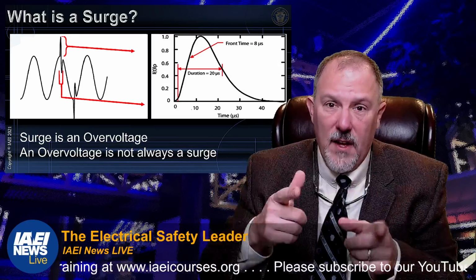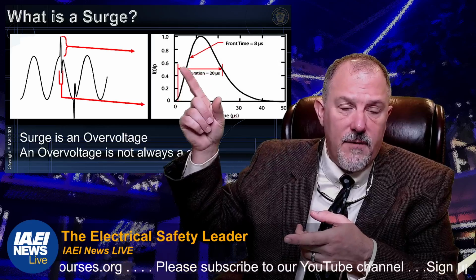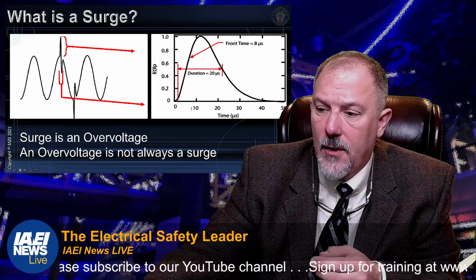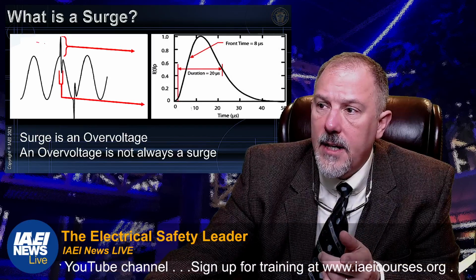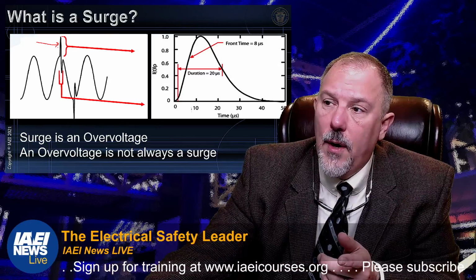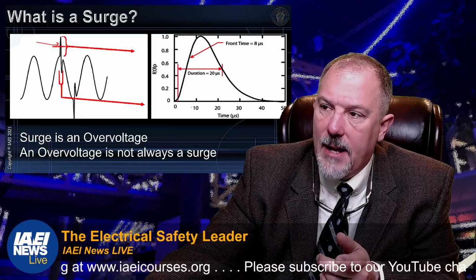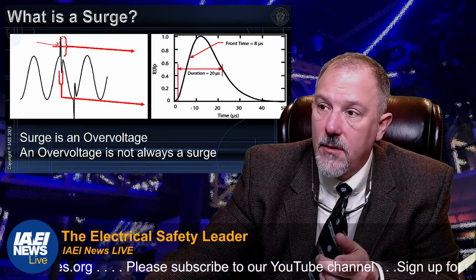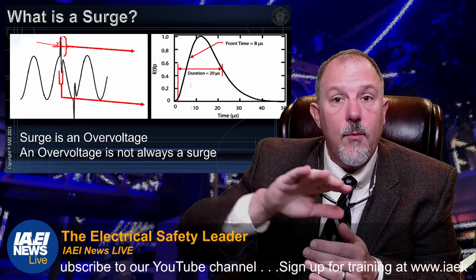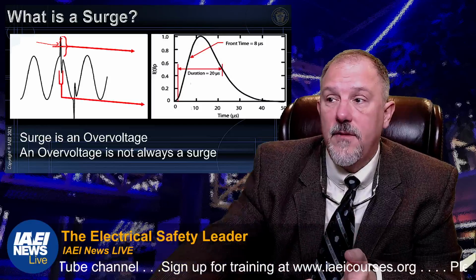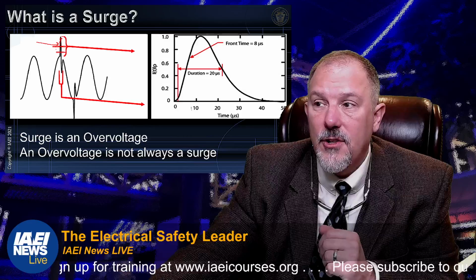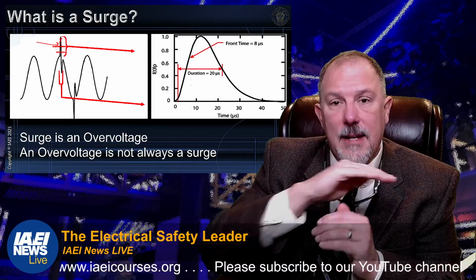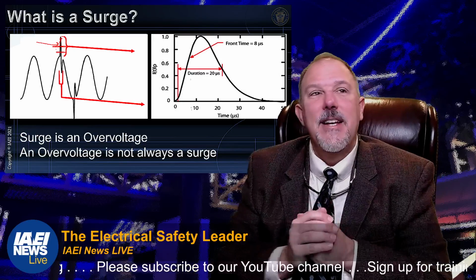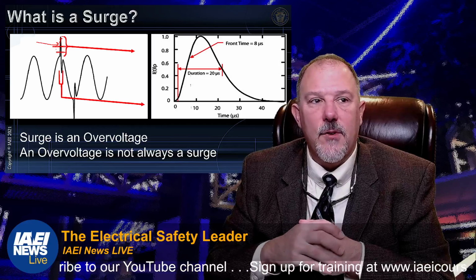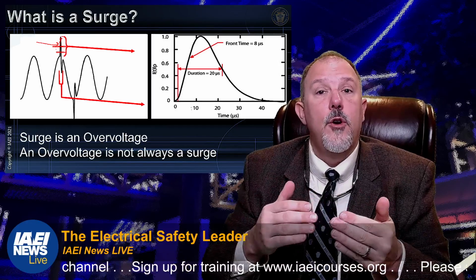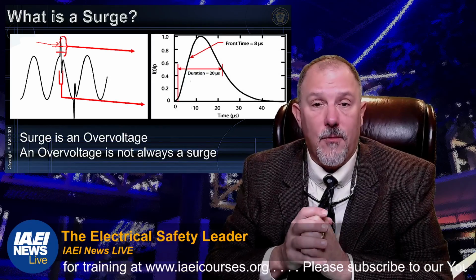If you think about what you're seeing here, you have this transient voltage that's up pretty high in the system. Say this event right here is at your service equipment. If you have a transient voltage device that clips that off at that point, making that go away, you're still left with a transient event over that sine wave that will propel itself, that will be seen downstream. And downstream devices might be able to clip these at lower values. So that clamping capability is an important aspect. Technically, we consider it as clamping that voltage peak, but technically we're shunting current to ground, right? We're moving the current around that it's generating as well.